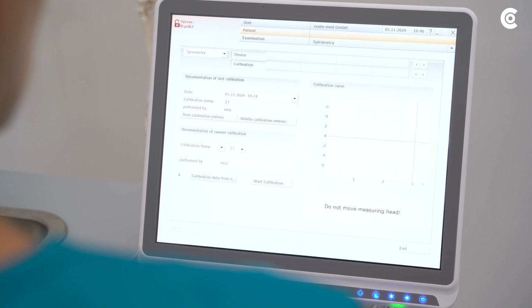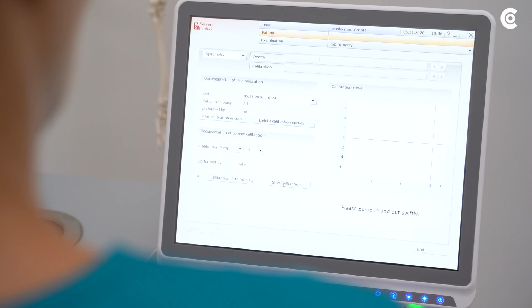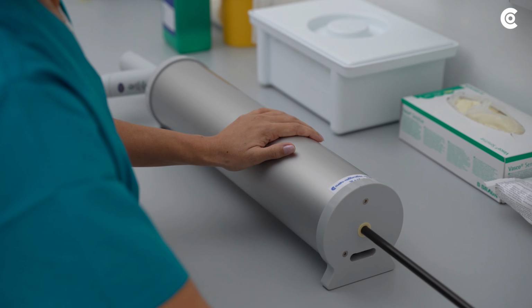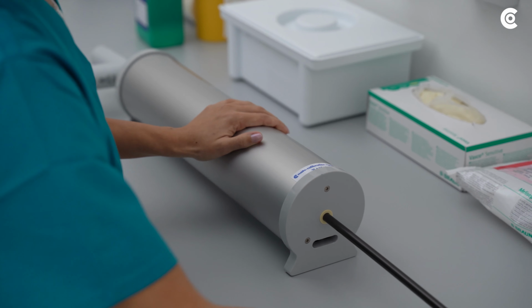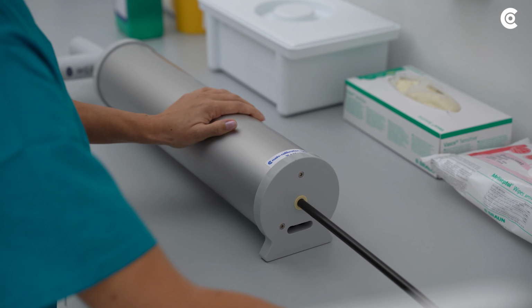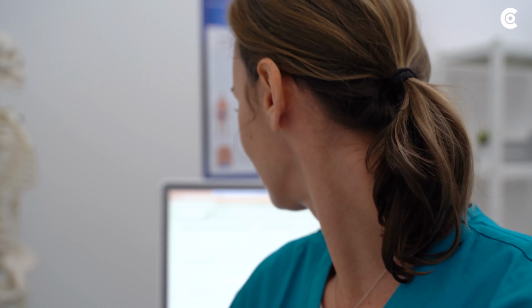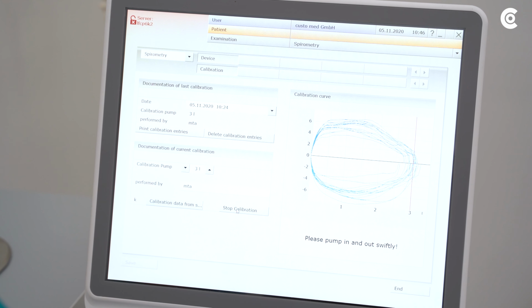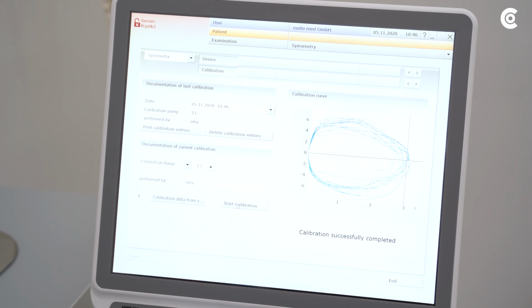Enter the volume of your calibration pump under Calibration and start the process. Pump air in a quick and constant movement through the Spiro Mobile until you see the message, Calibration successfully completed. The Spiro Mobile is ready for use again.